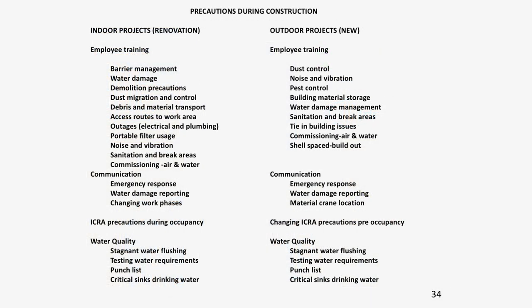Slide 34 essentially says there's a lot to know in indoor and outdoor projects. Outdoor projects have a variety of considerations, water damage being very important because we don't want our building wet before we occupy it. Water quality is also important on both sides, and it's really important to keep that water moving, even though it becomes expensive to just discard water. But we fill our pipes with water months before we occupy, and that stagnation helps build a biofilm, which is something that should be addressed in the construction phase.